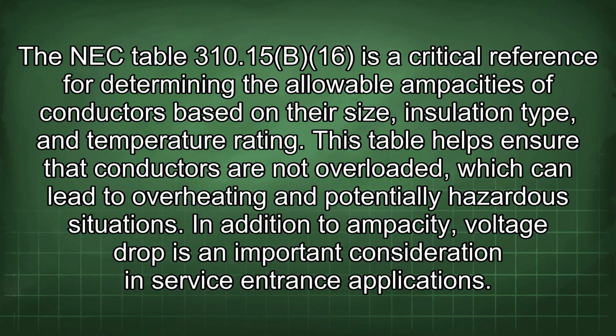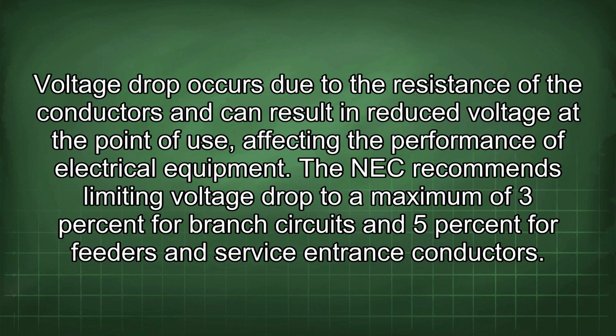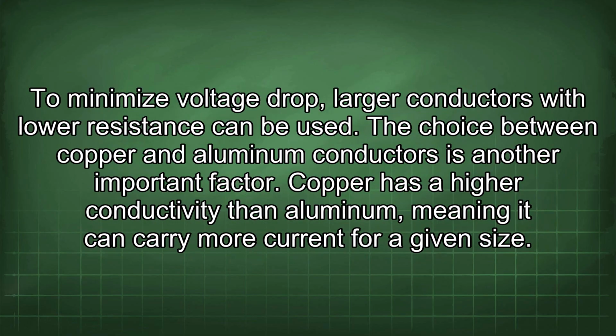In addition to ampacity, voltage drop is an important consideration in service entrance applications. Voltage drop occurs due to the resistance of the conductors and can result in reduced voltage at the point of use, affecting the performance of electrical equipment. The NEC recommends limiting voltage drop to a maximum of 3% for branch circuits and 5% for feeders and service entrance conductors. To minimize voltage drop, larger conductors with low resistance can be used.